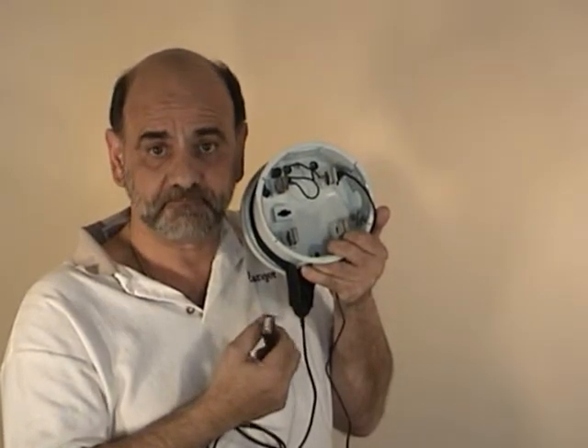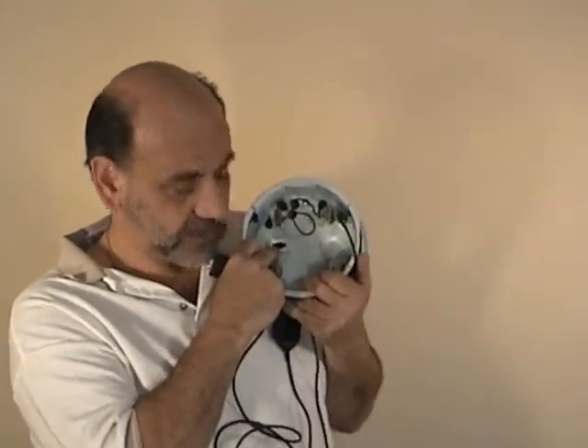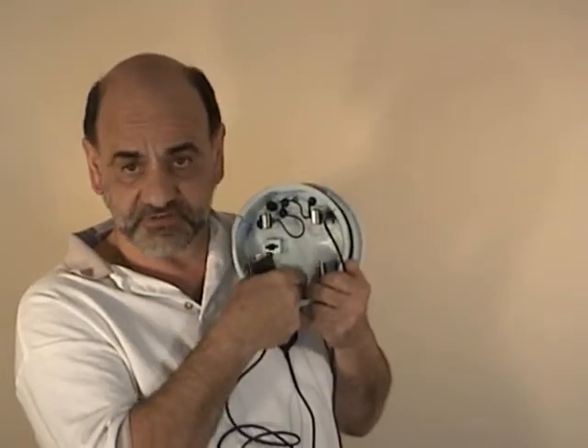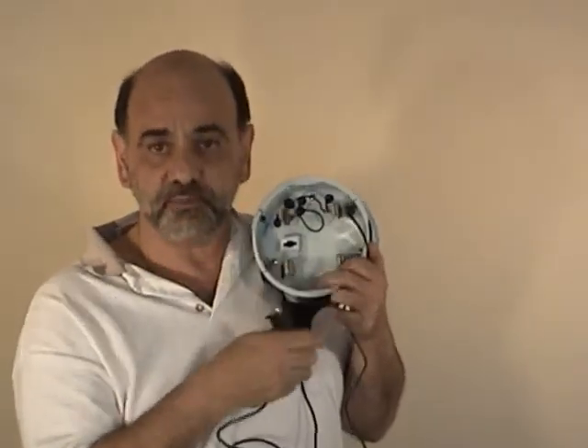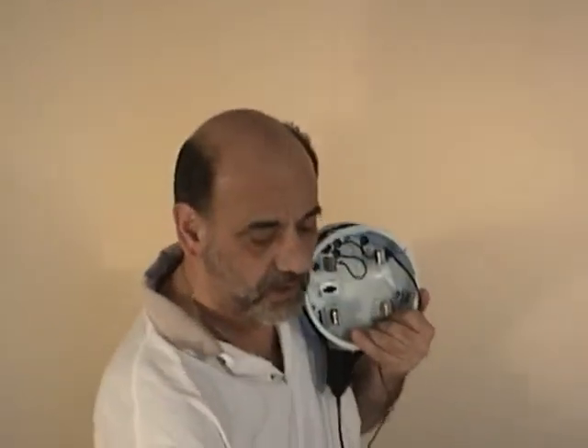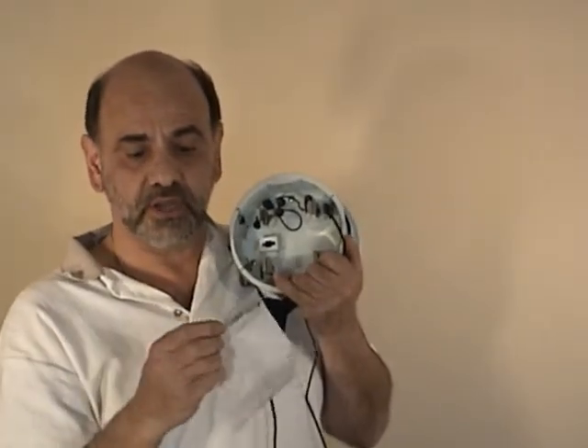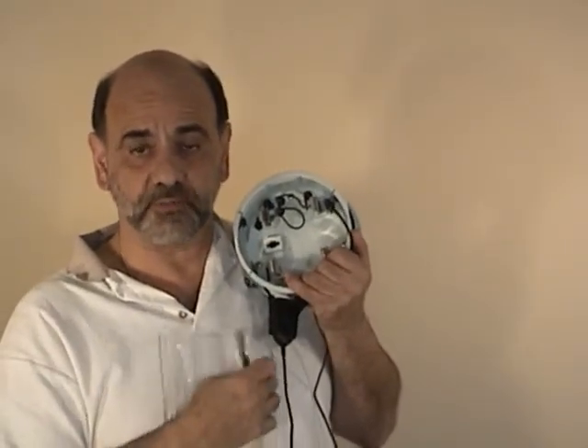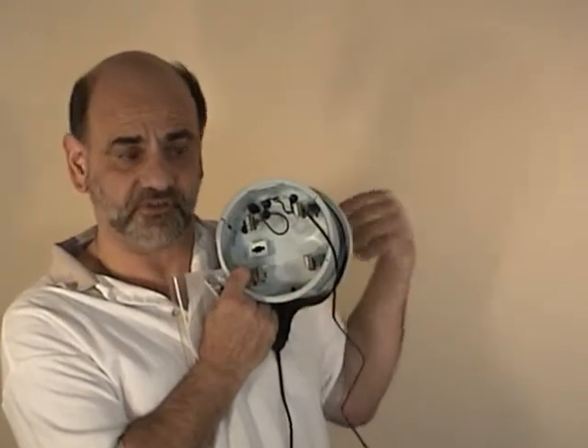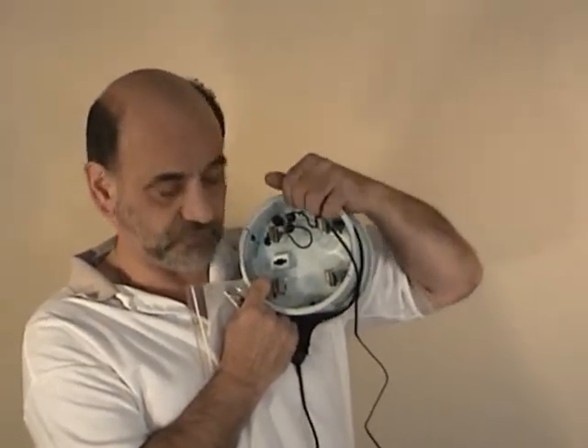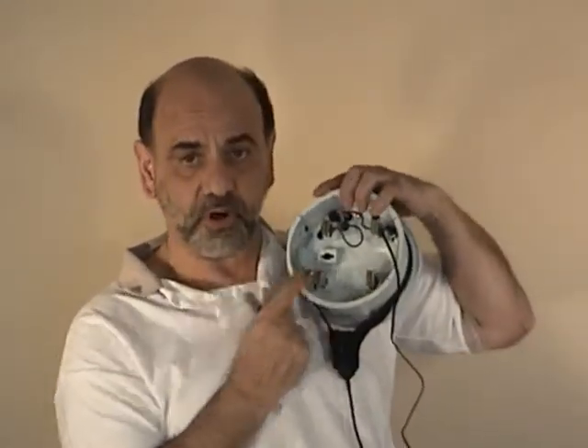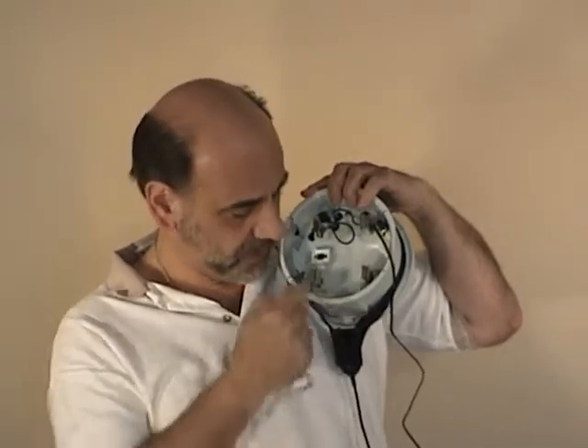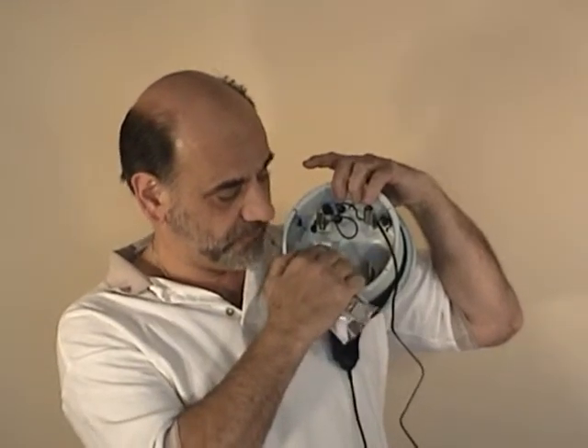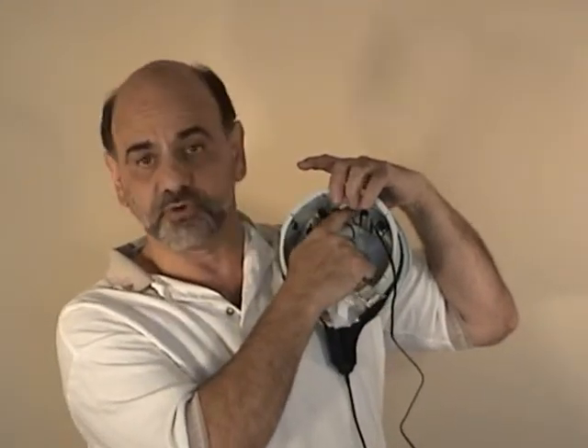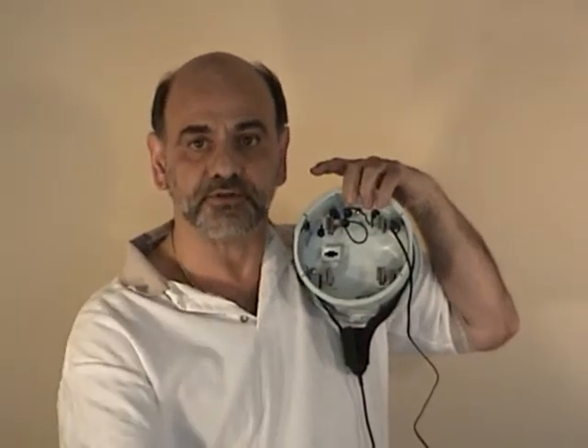And don't forget, we have the 9 o'clock position, and there will be a 6 o'clock position here where you can put the extra blade that we give you if you need to pick up a neutral, as opposed to using the neutral wire connection that was on the back. If you have a neutral blade, there's also a jumper included in here with a cotter pin that will allow you to jumper from this blade to the neutral connection on the inside of the unit.